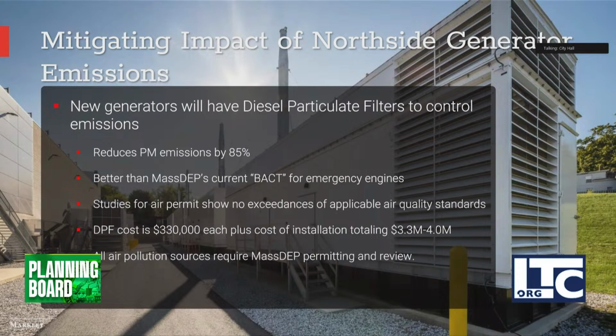In addition, these new north side generators being permitted now through DEP will have diesel particulate filters to control PM emissions. These DPFs, made by a company in Franklin called Rypos, reduce diesel particulate emissions by 85%, the California Air Resources Board standard. We've assumed 85% in our calculations, though I believe Rypos guarantees a higher number than that.